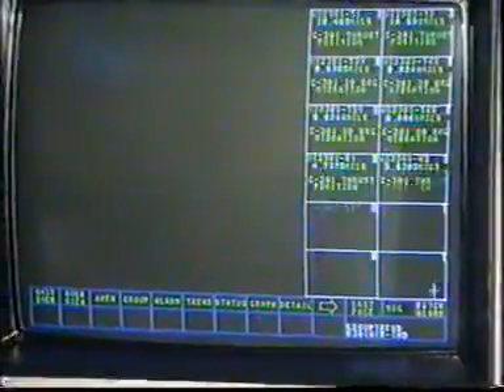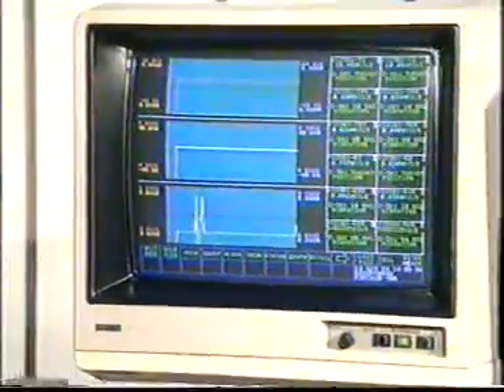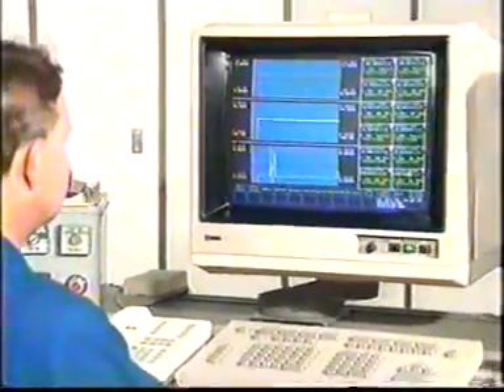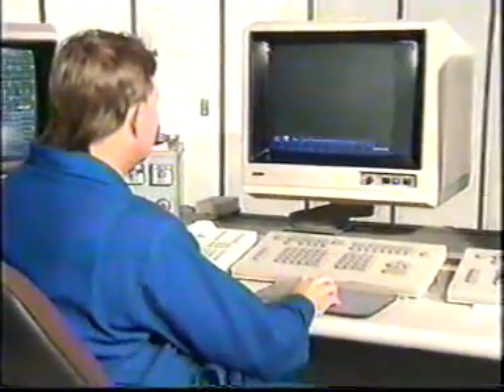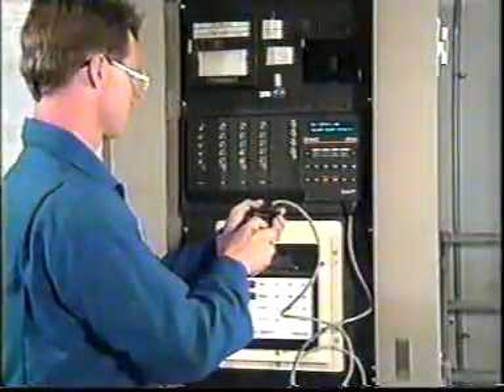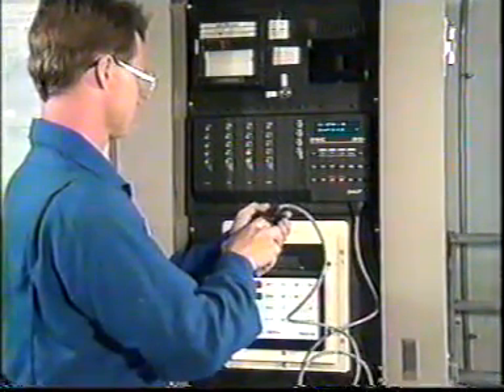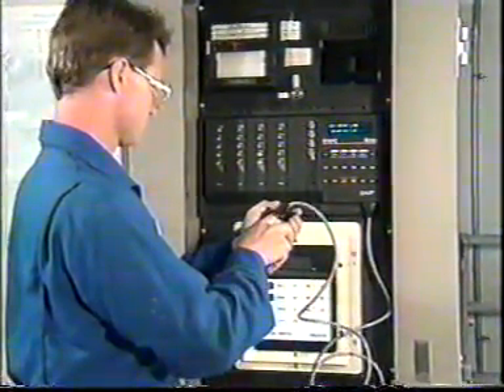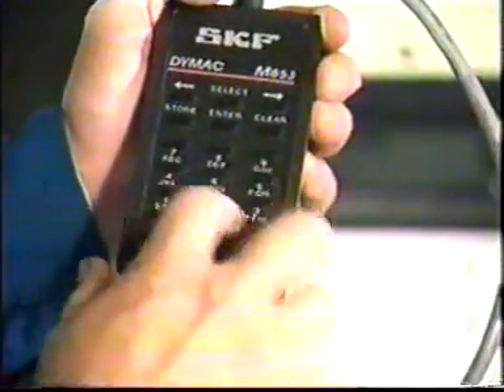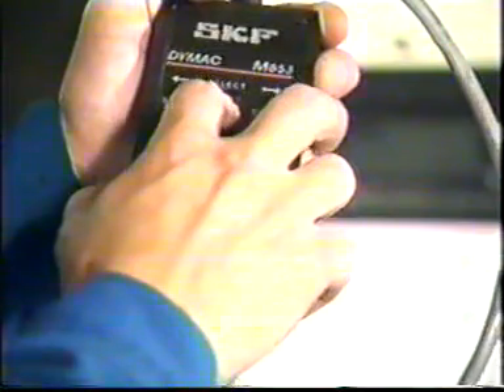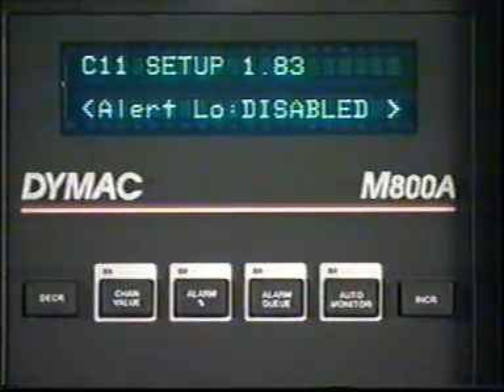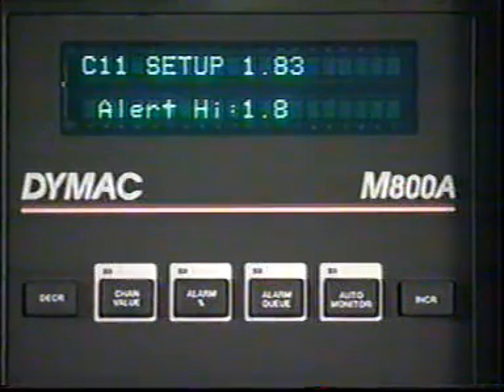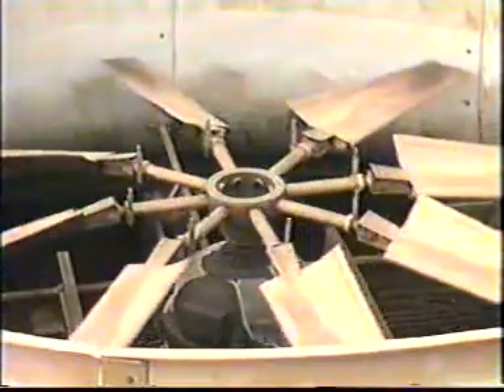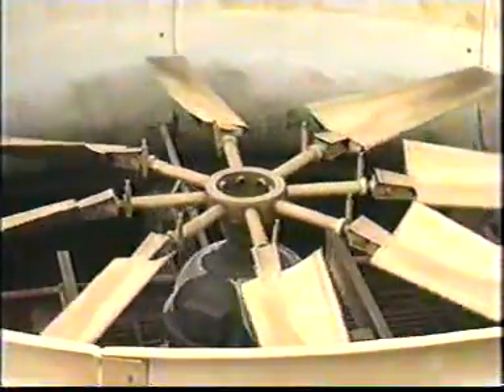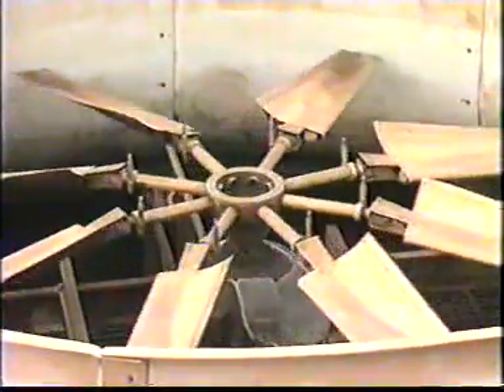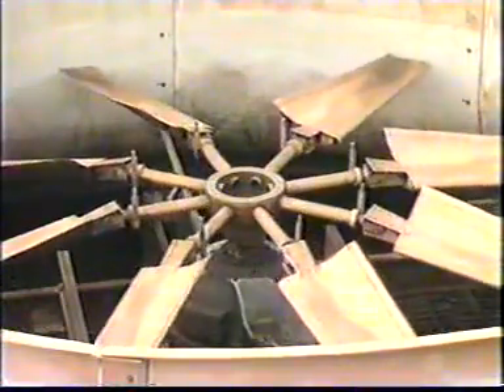Alarms are one protection method. An alarm may provide audible and or visual indication to operating and maintenance personnel that a piece of equipment has a vibration problem. Alarm values need to be set high enough to prevent spurious alarms. If an alarm happens with regularity, people will become complacent and not give it the attention it deserves. But the alarm needs to be set low enough so that there is time to investigate the problem before a failure happens. Another protection method is automatic shutdown. In some cases, it's prudent to shut the machine down instead of letting it continue to vibrate past a certain limit.